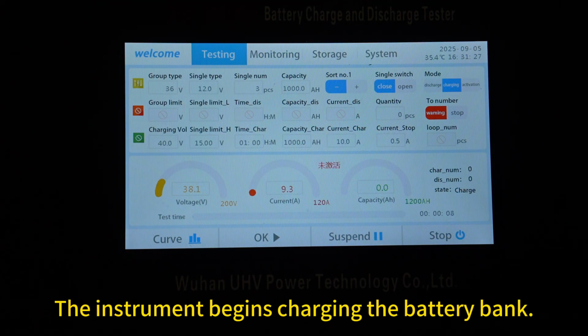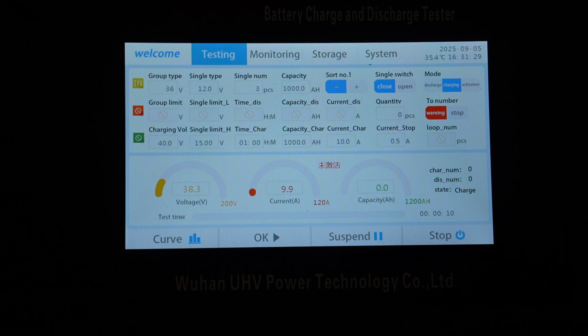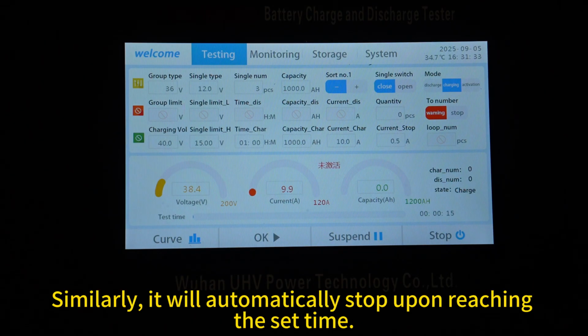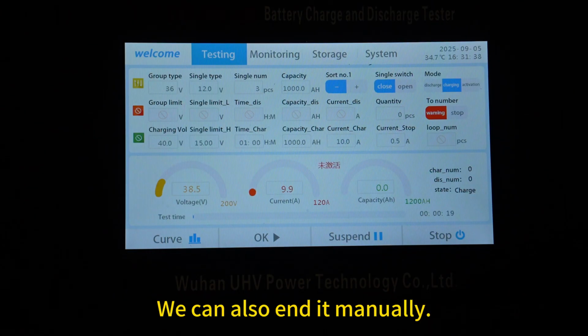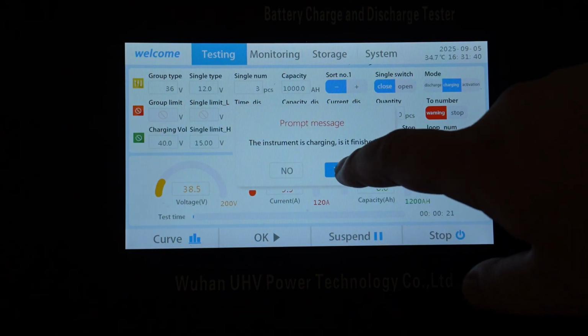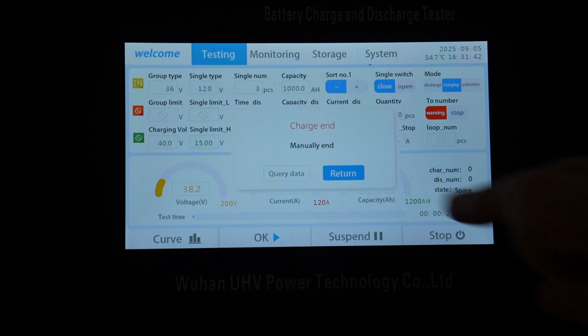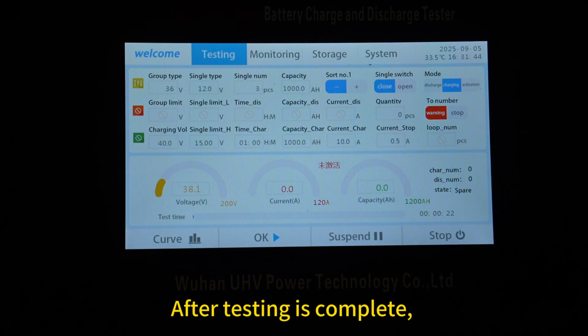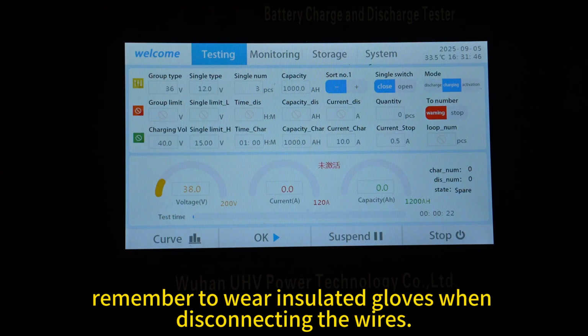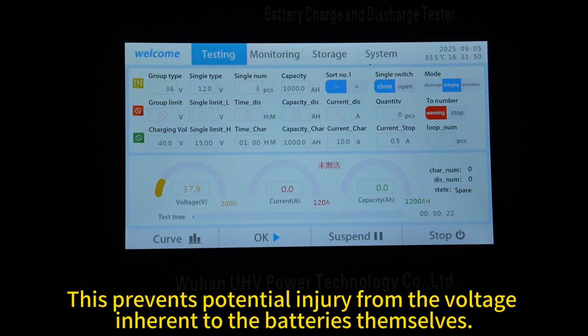The instrument begins charging the battery bank. Similarly, it will automatically stop upon reaching the set time. We can also end it manually. After testing is complete, remember to wear insulated gloves when disconnecting the wires. This prevents potential injury from the voltage inherent to the batteries themselves.